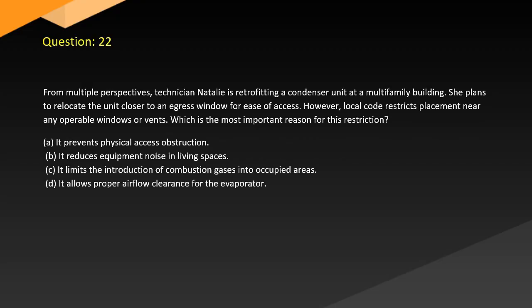Question 22. From multiple perspectives, technician Natalie is retrofitting a condenser unit at a multifamily building. She plans to relocate the unit closer to an egress window for ease of access. However, local code restricts placement near any operable windows or vents. Which is the most important reason for this restriction? A. It prevents physical access obstruction. B. It reduces equipment noise in living spaces. C. It limits the introduction of combustion gases into occupied areas. D. It allows proper airflow clearance for the evaporator.